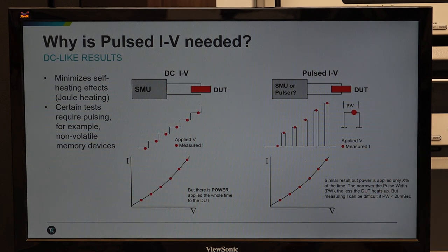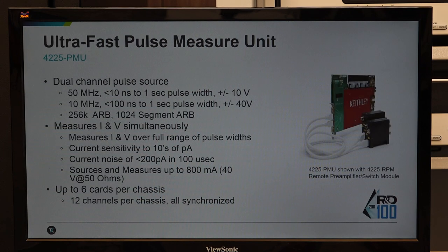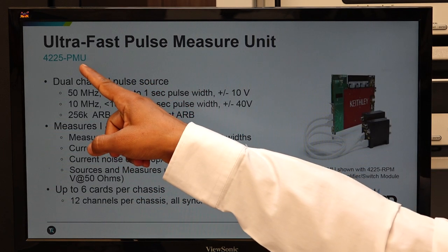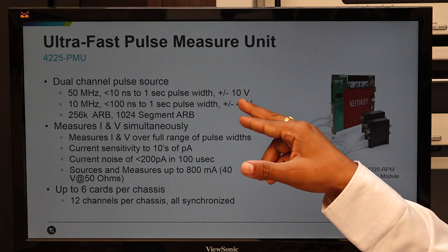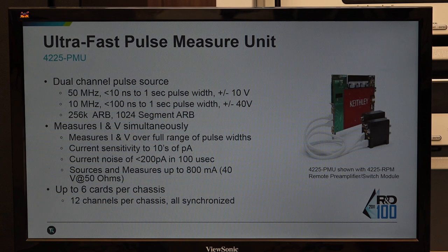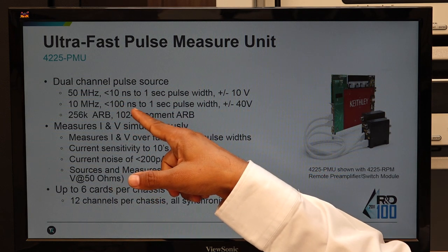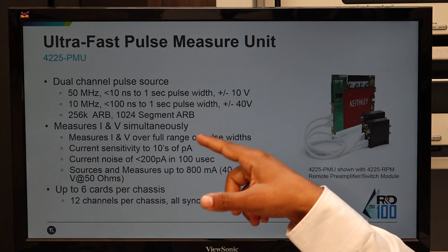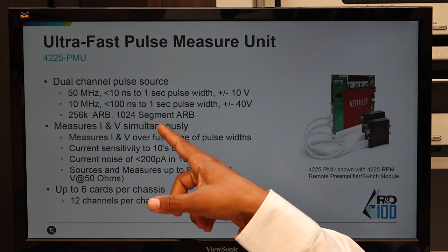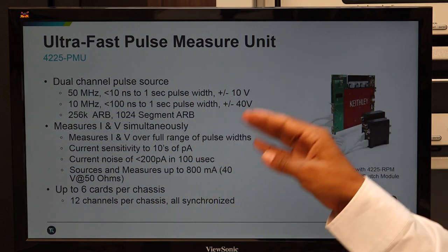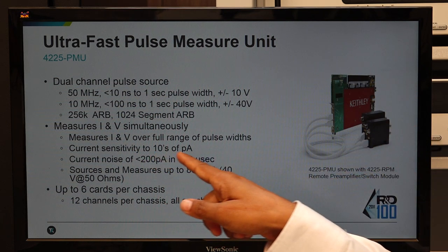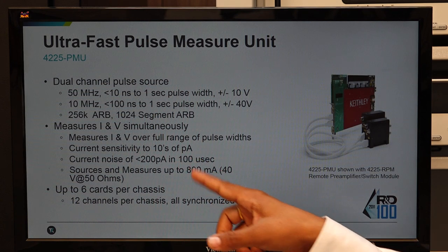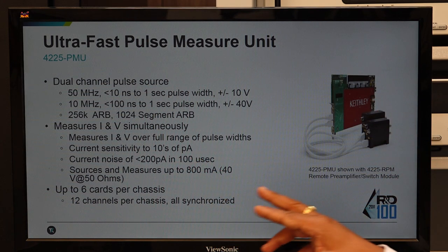When applying voltage in pulses and doing current measurement, measuring lower current much faster is another challenge. For these applications, Keithley Parametric Analyzer 4200 has the ultra-fast pulse source and measurement unit, which is the 4225 PMU. This unit comes with dual channel, supports two voltage ranges: 10 volt and 40 volt. For 10 volt, it supports 50 MHz pulse frequency — pulses from 10 nanoseconds up to 1 second. For 40 volt, pulses from 100 nanoseconds to 1 second. Current sensitivity of 10 picoampere on the lower side, and 800 mA on the higher side.